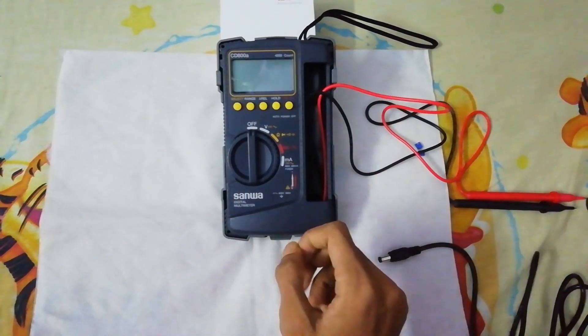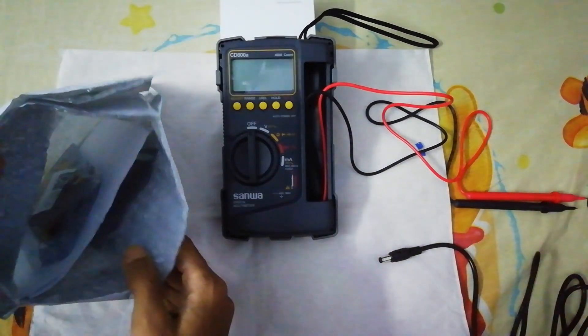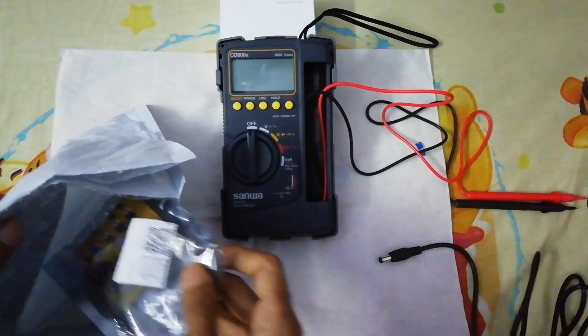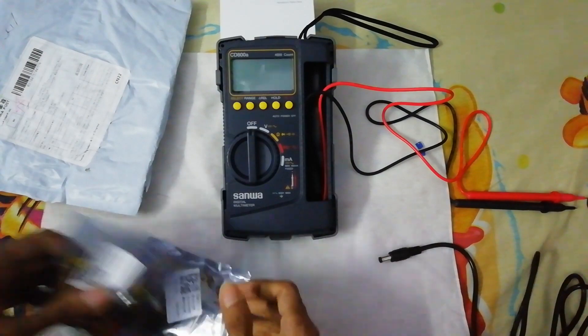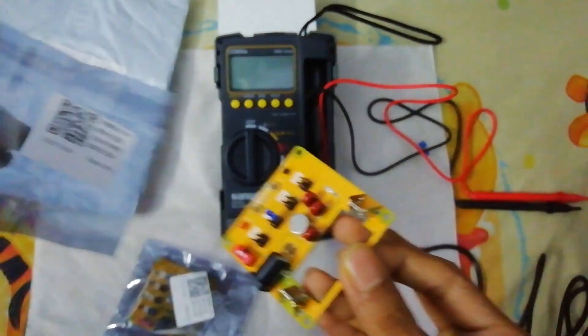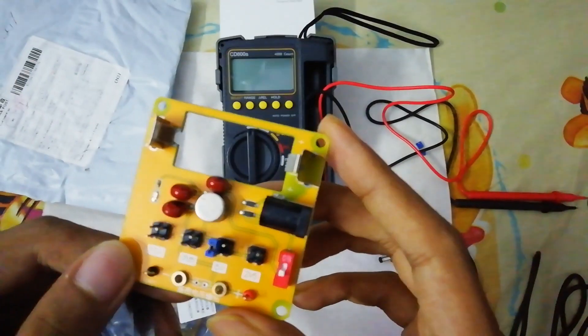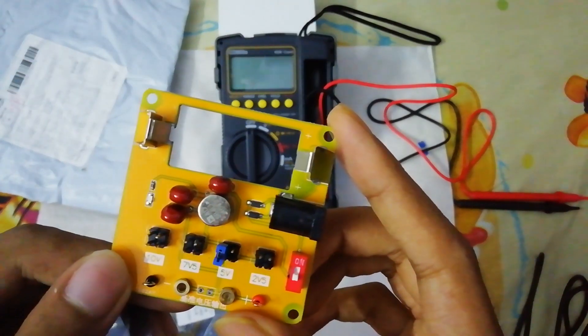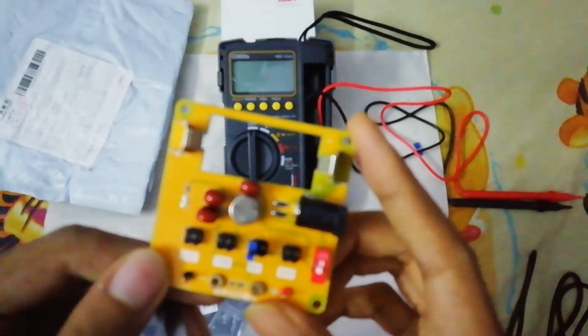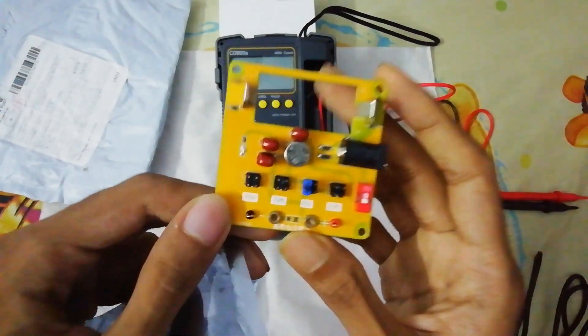Here are the voltage references. I have two voltage references I bought from Aliexpress, I will give you the link. This is an AD584 chip based voltage reference. This can measure up to 10.00 volt. The lowest range is 2.5 which is 2.499, then 5 volt which is 5.00, then 7.5 which is 7.500, then 10 volt which is 10.00.